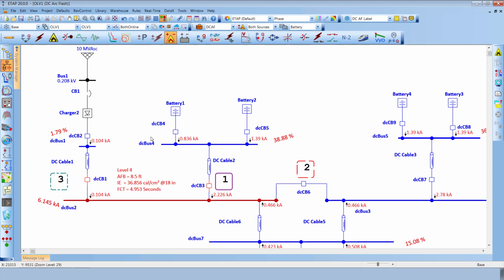Upon finishing this particular condition, in ETAP 20, we have introduced a new concept of calculating the incident energy, accounting for the de-energization of the source from its corresponding source protective device sequence of operation. Or in other words, ETAP now has the ability to calculate the incident energy per stage depending upon the sequence of protective devices that de-energizes each source path of a fault.